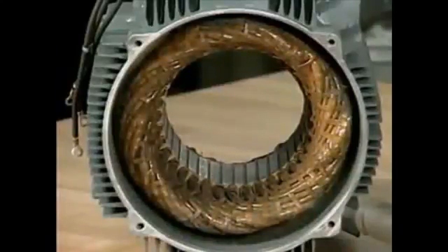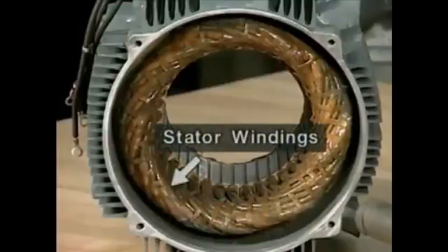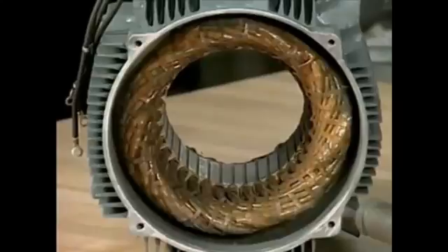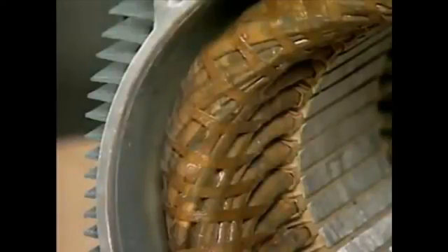This is a stator from an AC motor. The end bells and the rotor have been removed to see the stator better. The stator contains several coils of wire called stator windings that surround the rotor. Current flow through the stator windings produces magnetic fields. The windings have been dipped in an insulating varnish and then baked.